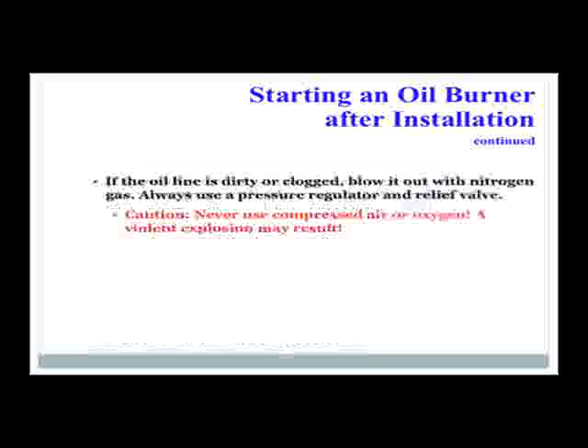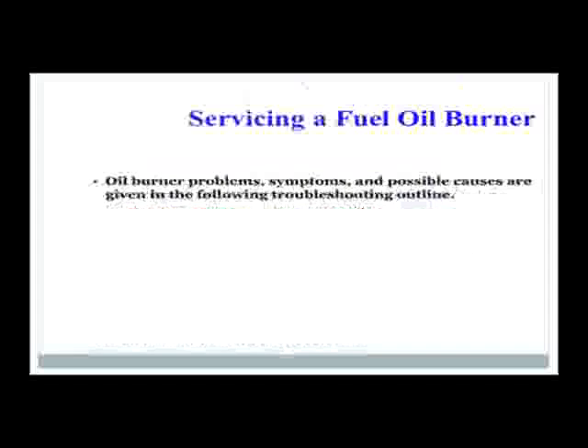If the oil line is dirty or clogged, blow it out with nitrogen gas. Always use a pressure regulator and a relief valve. Don't use compressed air or oxygen. A violent explosion may result. Again, air contains oxygen. Oxygen supports burning.